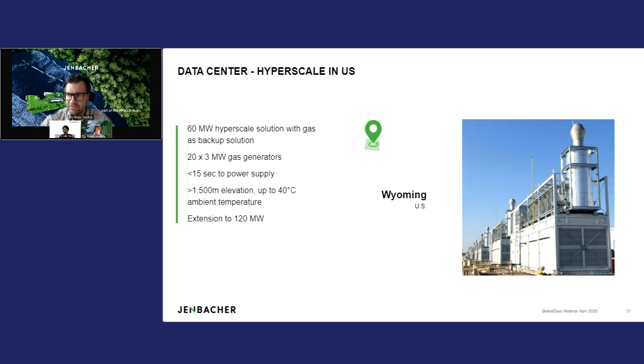This is a unique setup with the same footprint, which was a main decision point for the client. Also, unlimited operating hours, because he can take the data center off the grid if required — he has agreements with the local utility that he might need to load curtail, taking the data center off the grid for certain peak times. Secondly, far lower emissions, 90 to 95% lower compared to a diesel backup solution.